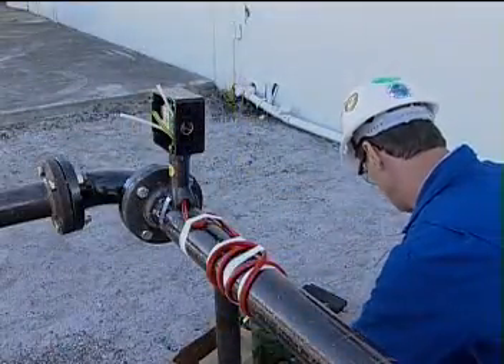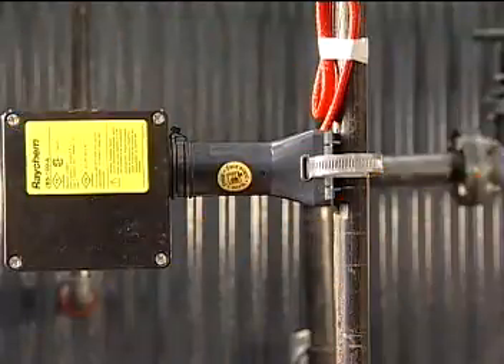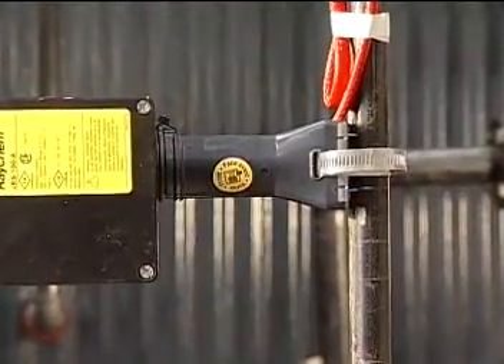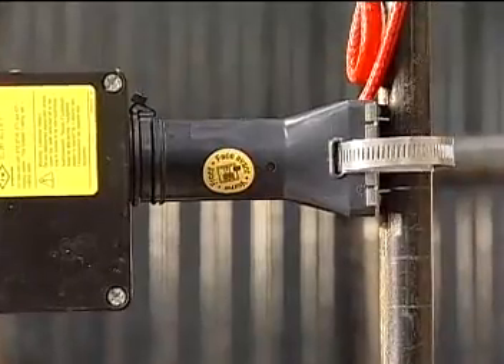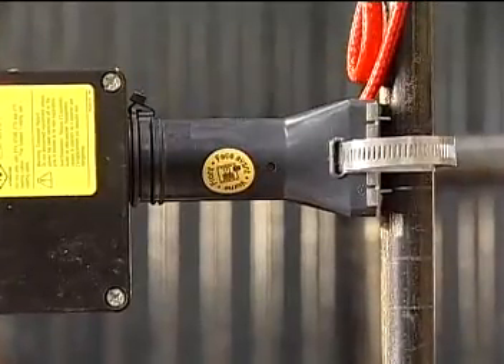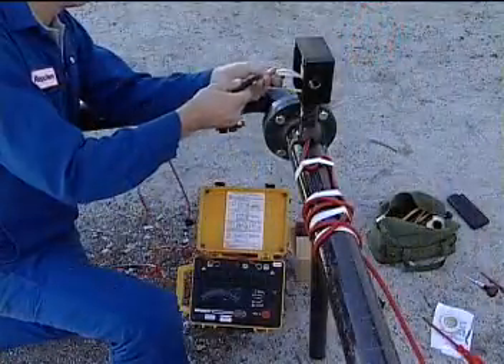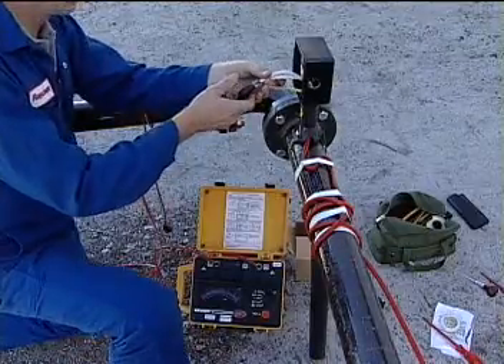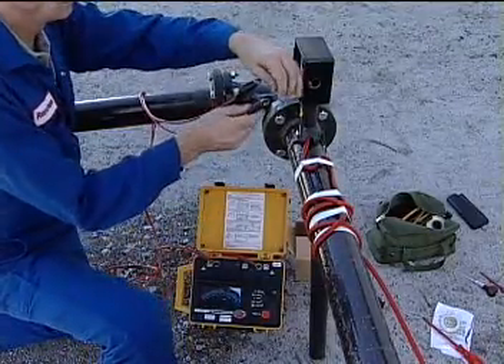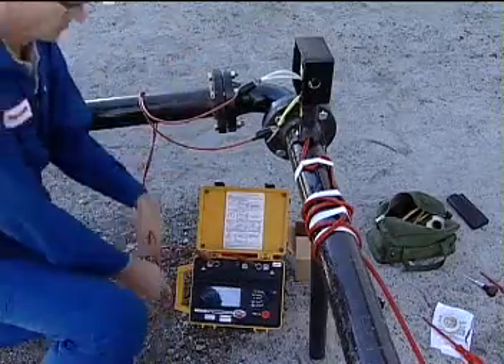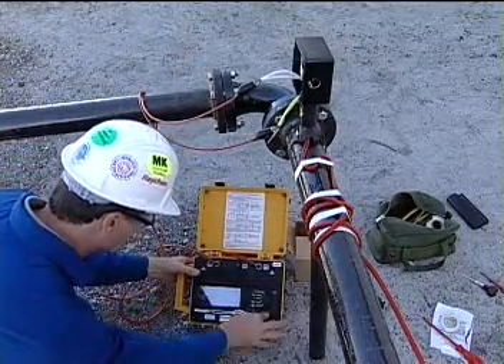Use appropriate sized pipe straps. Tape the service loop to the pipe. A small pipe adapter has been included in each kit for use on 1-inch pipe or smaller. This prevents the cable from being crushed by the stand. When all the connections have been made, conduct an insulation resistance test of the cable to ensure that the cable was not damaged during the installation, and record the results.